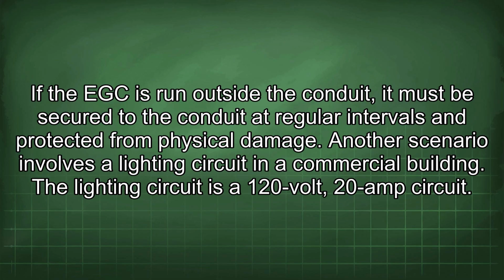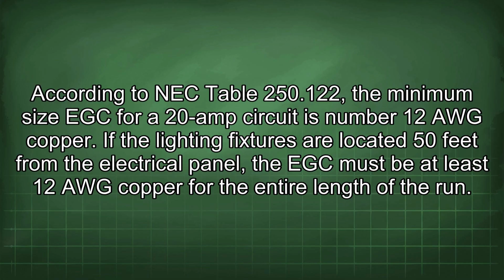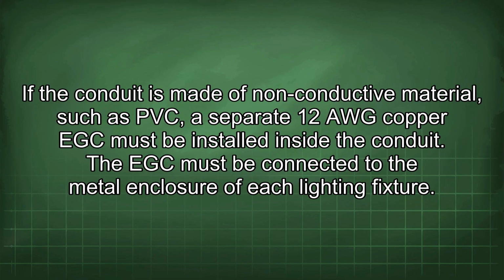Another scenario involves a lighting circuit in a commercial building. The lighting circuit is a 120-volt, 20-amp circuit. According to NEC Table 250.122, the minimum size EGC for a 20-amp circuit is number 12 AWG copper. If the lighting fixtures are located 50 feet from the electrical panel, the EGC must be at least 12 AWG copper for the entire length of the run. If the conduit is made of non-conductive material, such as PVC, a separate 12 AWG copper EGC must be installed inside the conduit. The EGC must be connected to the metal enclosure of each lighting fixture.